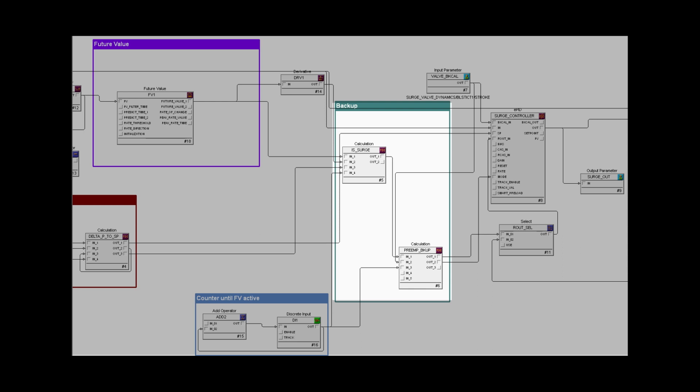This control strategy also contains logic to detect imminent surge. Whenever the predicted suction flow value is below the unmodified set point, or if the derivative exceeds a critical negative value, a flag gets set triggering the open-loop backup for 10 seconds. Once the open-loop backup is cleared, the PI controller transitions from R-out to auto.